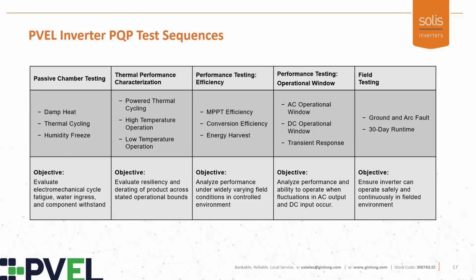Moving to performance testing, AC operational window. The intent of this series of tests is to understand if products derate as a function of AC voltage, which includes the low voltage ride-through in many areas today, DC voltage, because there's a host of different stringing configurations for any given inverter, and transient response. How does the device behave under these transient conditions like low and high voltage ride-through and like low and high frequency ride-through?